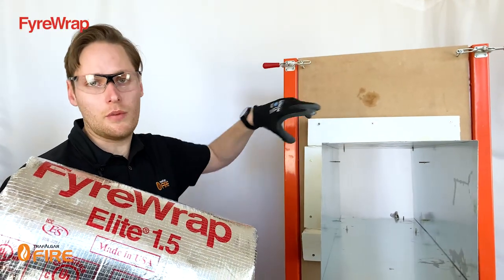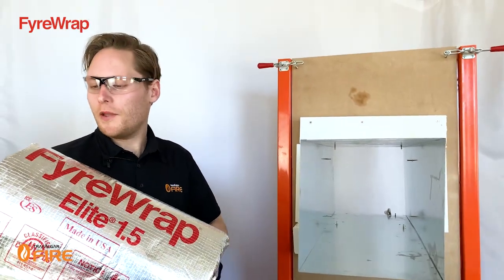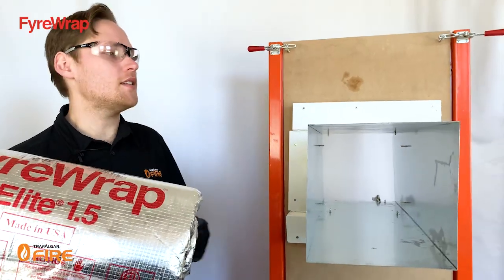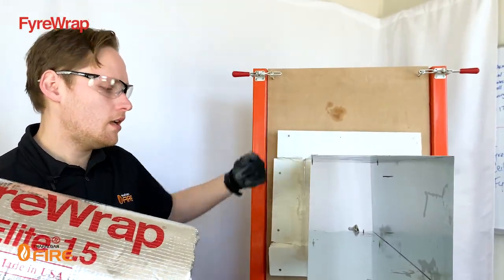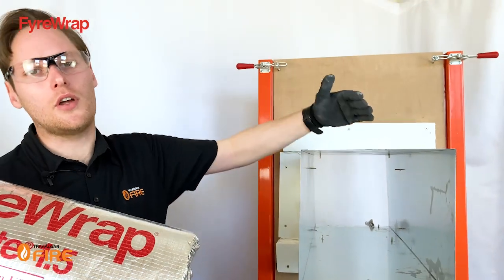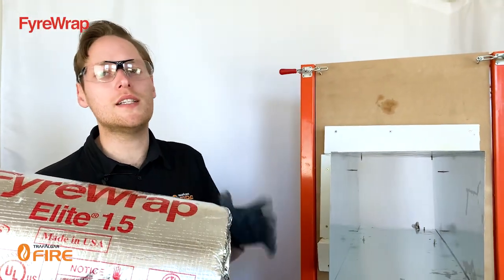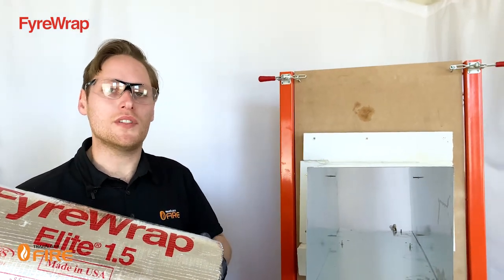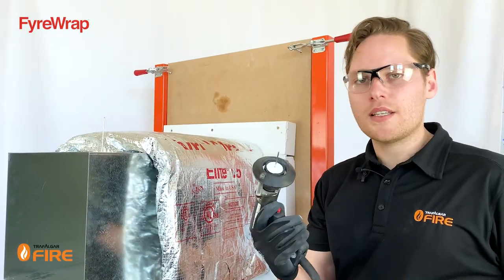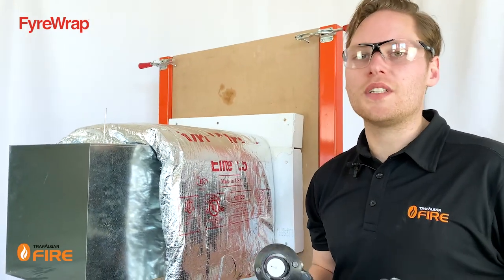Now that we've got the MaxiLite perimeter in place, it's time to wrap the duct. To measure the FyreWrap, take the outside perimeter of the duct all the way around and add an extra 100mm allowance for an overlap. There are two ways to install the fire wrap onto a duct: the first is using pins and a pin welder, and the second is using metal straps. I'm going to show you both options.